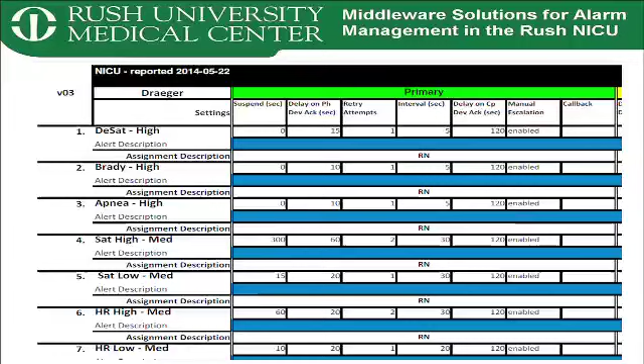And the nice advantage of that is that if the patient drops 10% below the lower limit, then you can change the priority. So if you have a big delay on your lower sat limit, by the time it gets down to 10% below it, then it can go instantaneous. And so we set these up, and there are all these different parameters that you can set. This is for one of the nurse call systems, and we set all of those up as well.